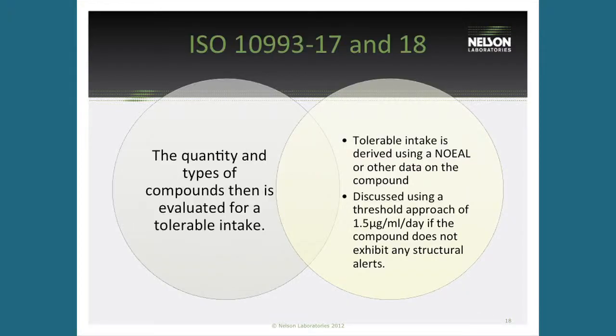The limit we're looking at for ISO 10993 is a threshold of 1.5 micrograms per mL per day. We've taken the most genotoxic compounds and looked at what levels represent safety for those compounds on a device. We've shared this information with the pharmaceutical industry and put a limit at 1.5 micrograms per mL per day — meaning if all compounds coming off your device are below that threshold, we shouldn't have to worry about genotoxicity. There's potential that we do the chemical analysis, evaluate how much is present, and if all compounds are below 1.5 µg/mL/day, we can eliminate the mouse micronucleus test and just do the in vitro tests. Right now this is not in the standard, but we're talking about putting this threshold in as either a standard itself or as a guidance document — something to help eliminate further animal testing.